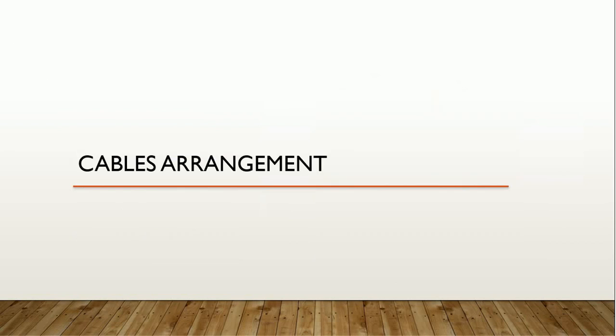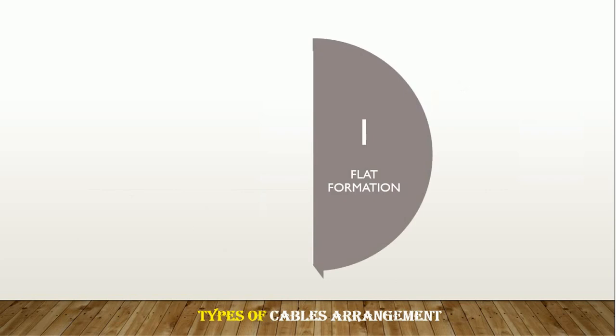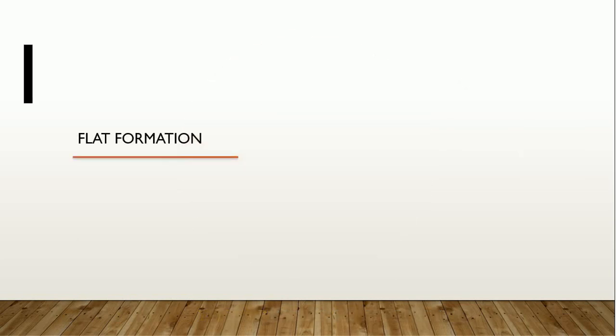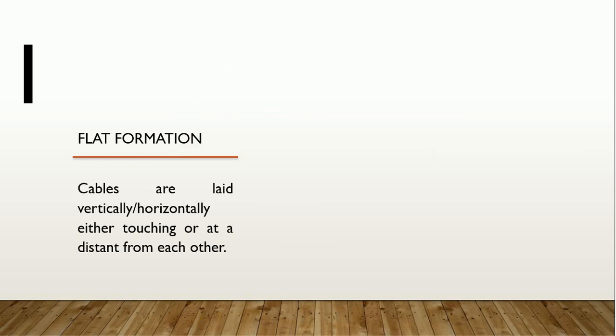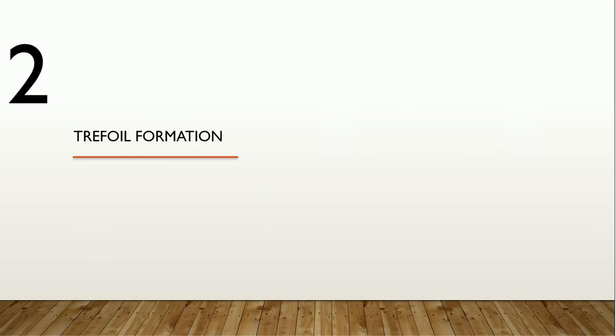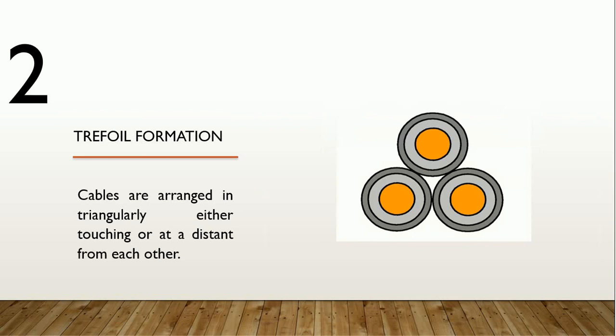In the next slide, we'll talk about cable arrangement. Cables are arranged in two different formations: flat formation and trefoil formation. Flat formation means cables are laid vertically or horizontally, either touching or at a distance from each other. While trefoil formation, the cables are arranged triangularly either touching or at a distance from each other, similar to this diagram.